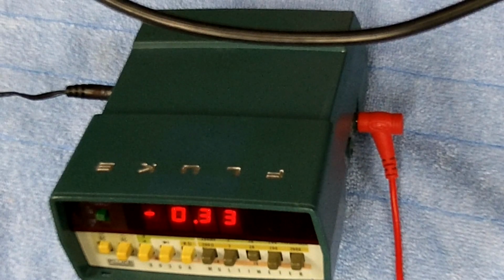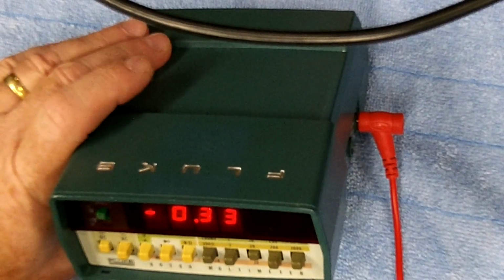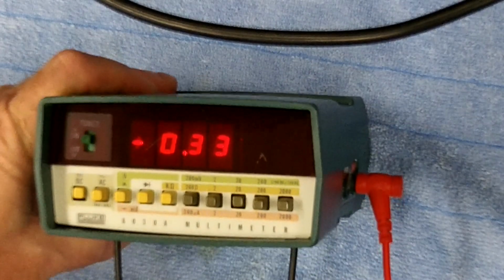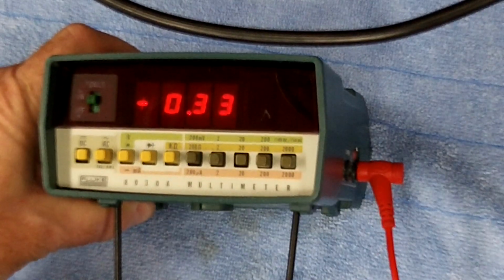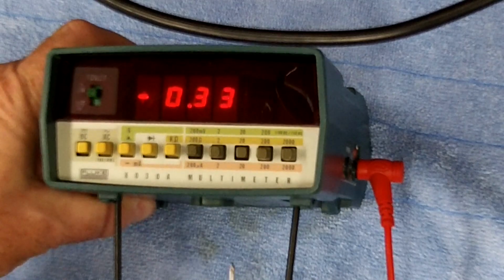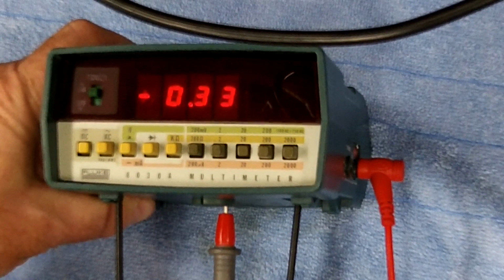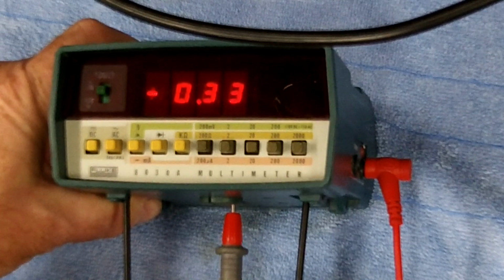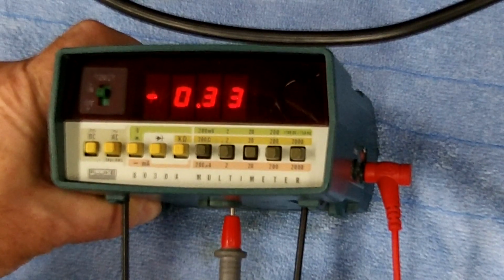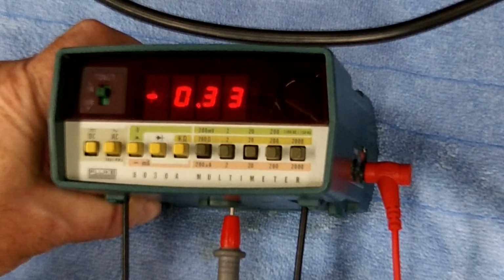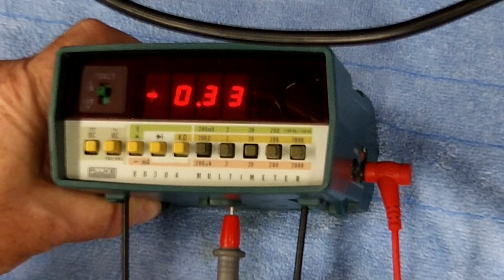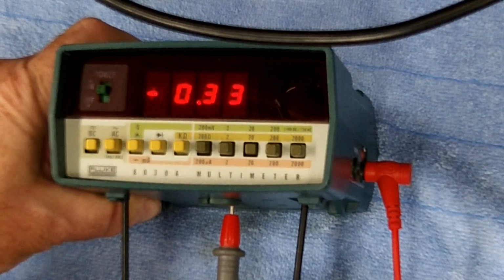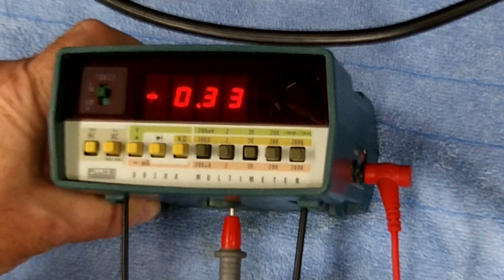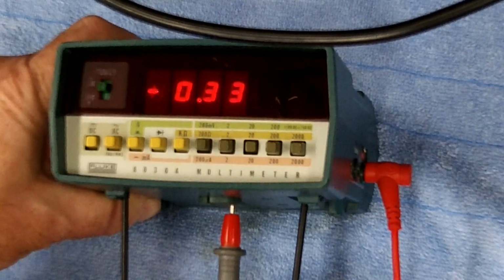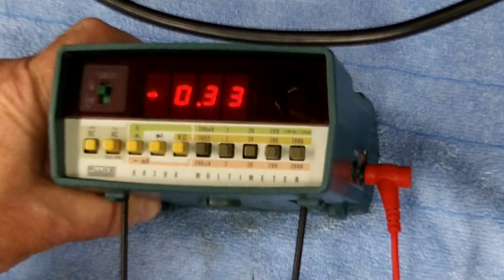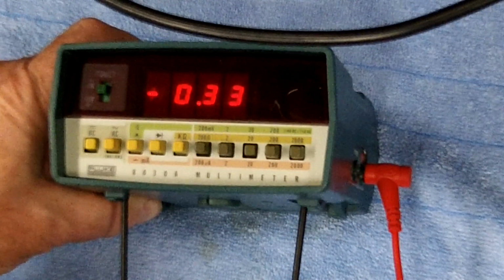Insert the probe at the test lead into the BTRY test hole in the bottom of the 8030A. Trying to keep you guys in frame so you can see what's going to go on here. I'm going to put this in the test hole. And nothing. It's not doing nothing. Says the display will indicate the battery voltage between 4 volts and 5.8 volts. Alright, we got nothing. It's not changing at all. Okay. Let's go to the next one.